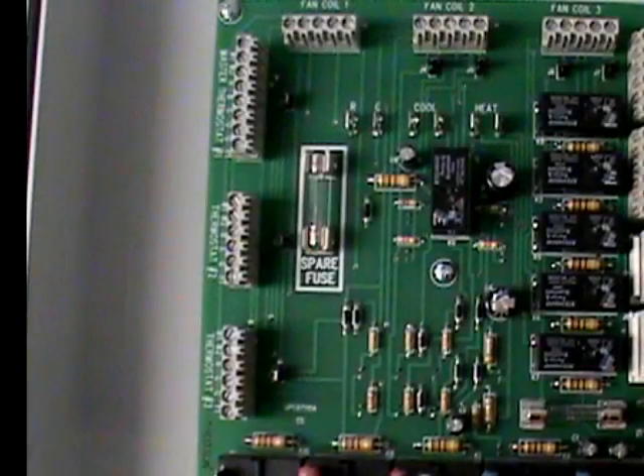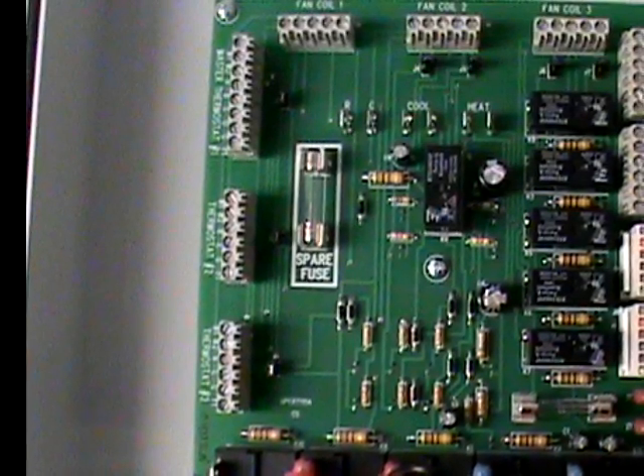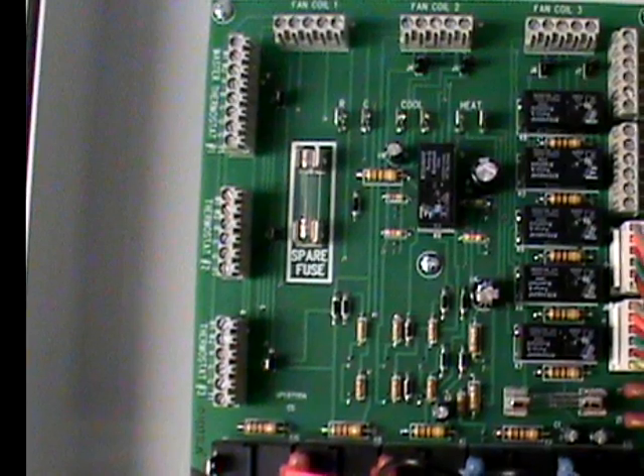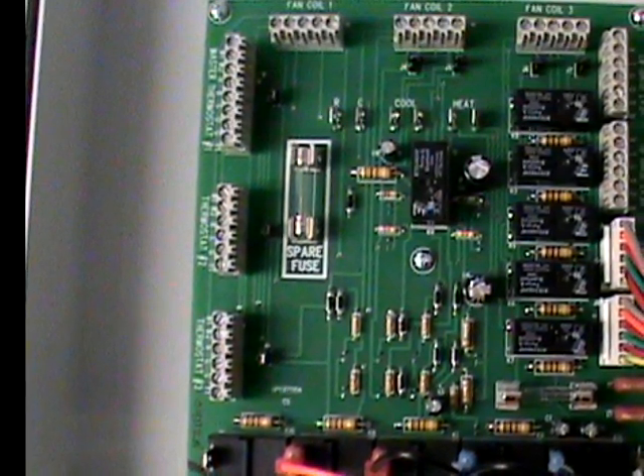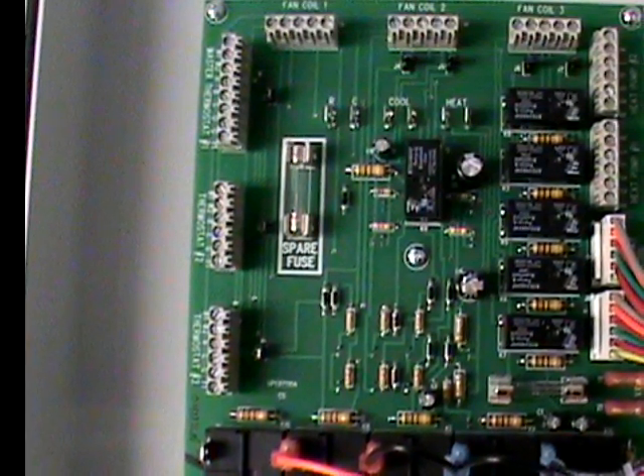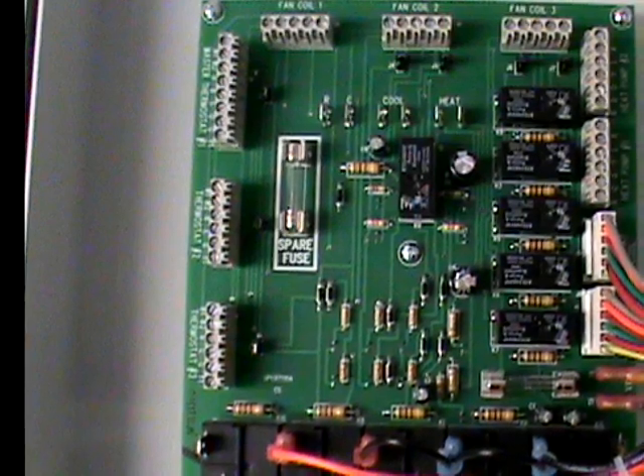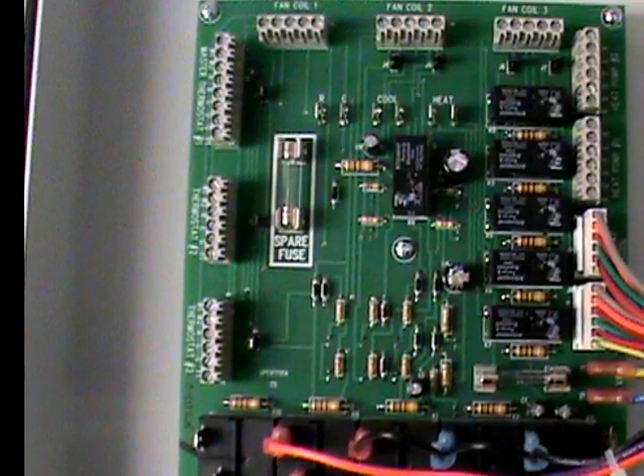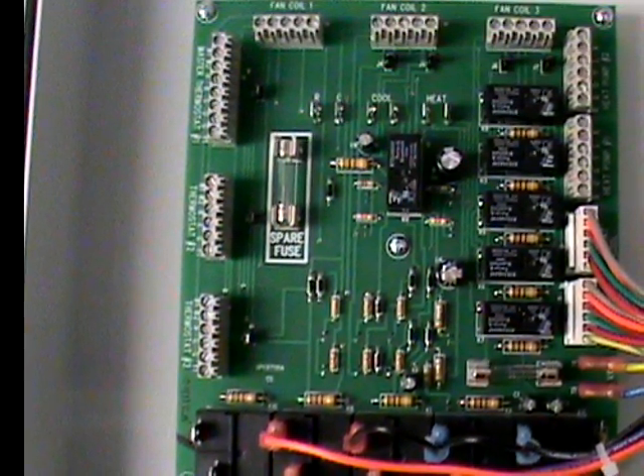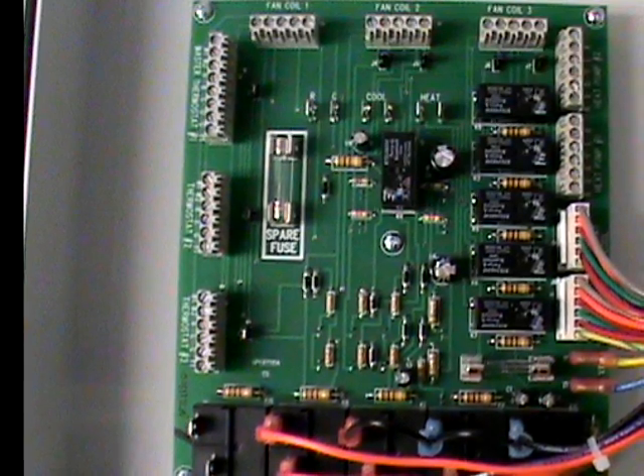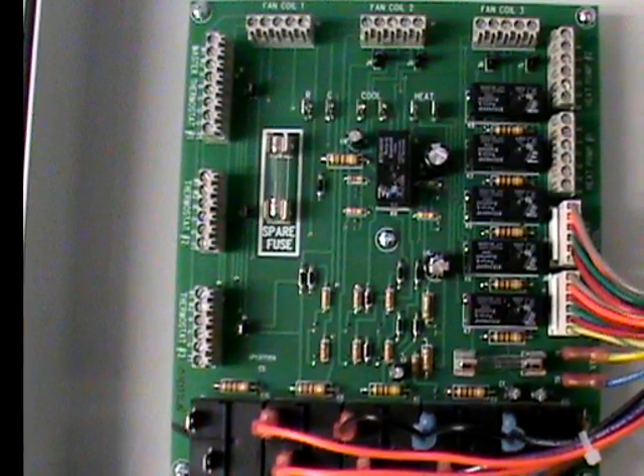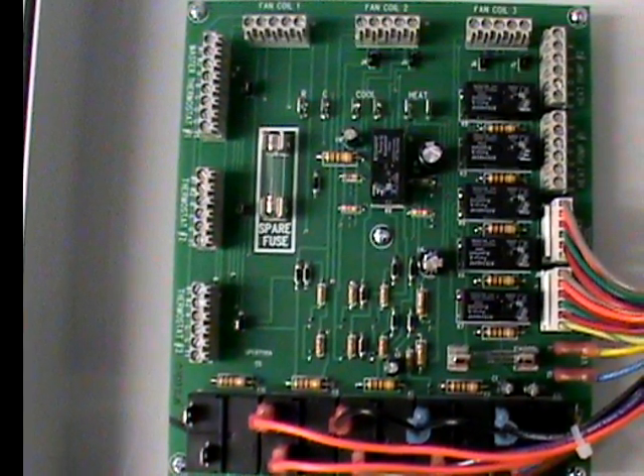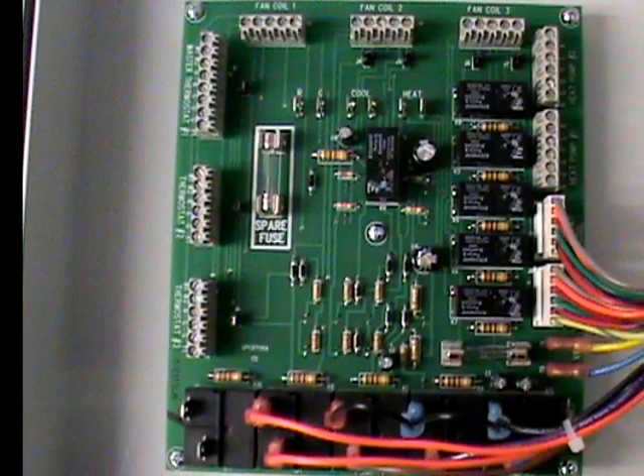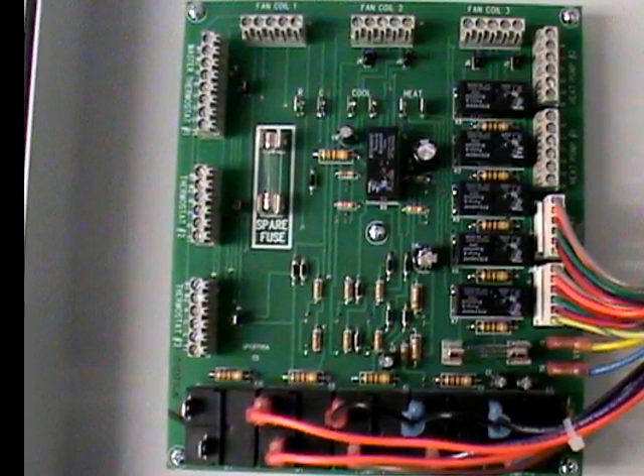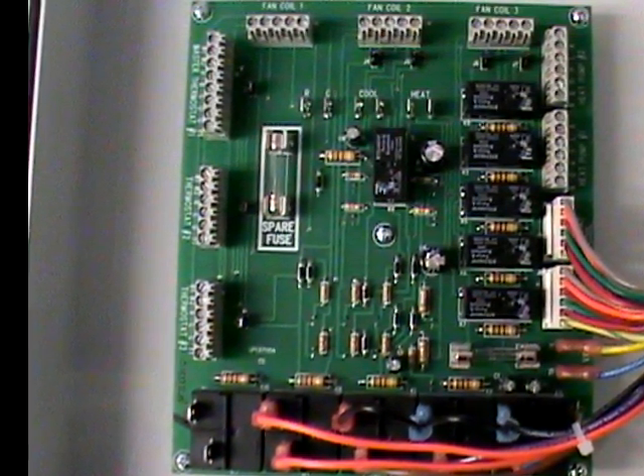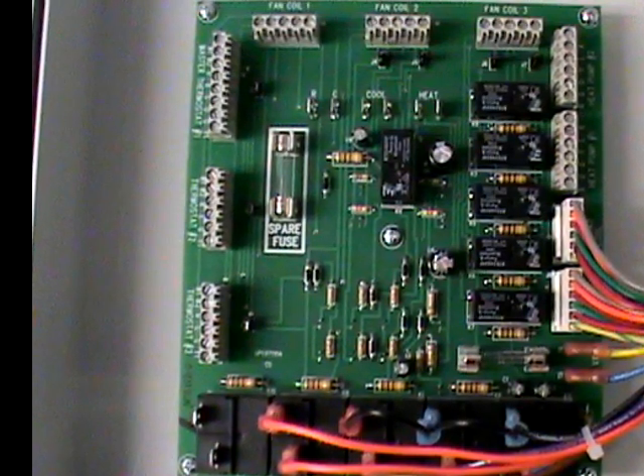Down the left side of the circuit board are the thermostat terminal blocks 1, 2, and 3. Each thermostat connects directly to the corresponding fan coil terminal block for low voltage isolation. When radiant floor zones are needed, then fan coil terminal blocks 2 or 3 will be left blank and the jumpers connected to provide 24 volt power to the corresponding radiant floor thermostats.